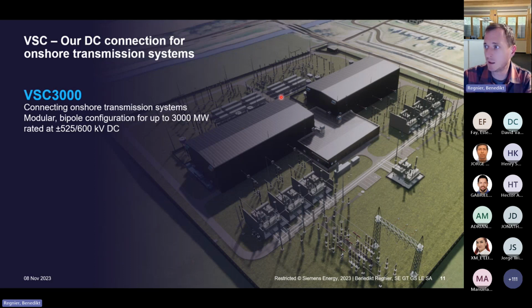We can see the DC yard here is outdoor, and only the converter is indoor, which is the bare minimum that needs to be indoor, obviously. The AC yard is outdoor, and the transformers are also outdoor. And we have a very big control building as a single floor building. That is always the cheapest solution. But this layout is only possible if we have no real space constraints or permitting constraints.